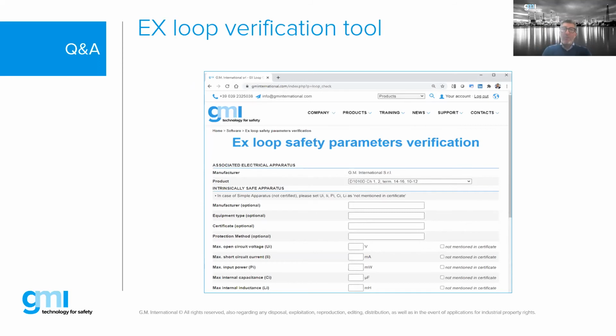We have a question, Bob, that we came across only in some parts of the world. There's a requirement that says when the inductance of the barrier is more than a certain value over that of the field device, you have to reduce the parameters by 50%. So you're basically reducing the distance of the cable you can use.